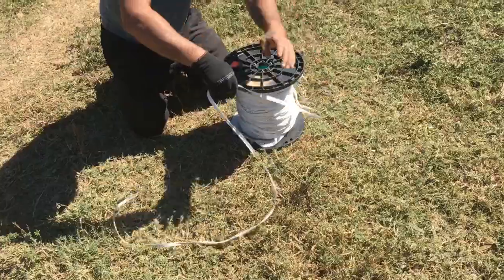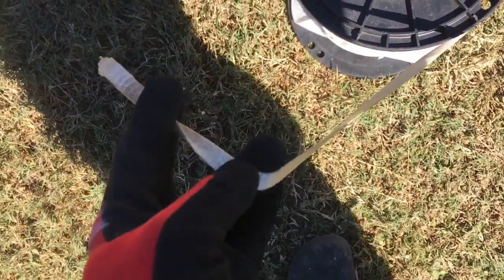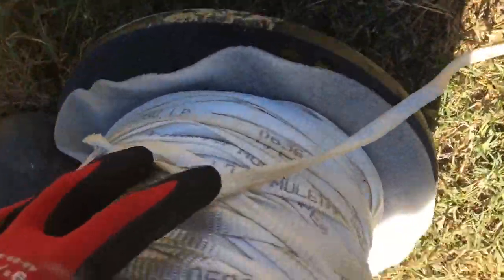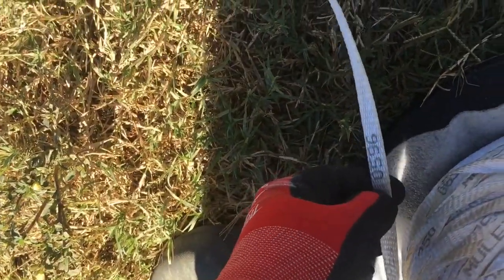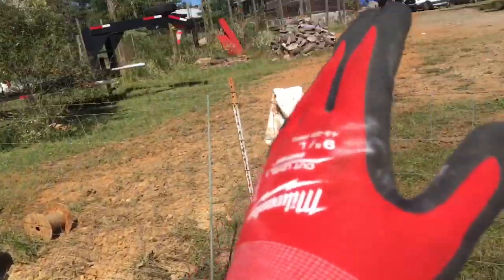Antonio, this is called mule tape — can I see it? This is the cord they're using to pull. This is for pulling electrical. You can also call it pull cord, but it actually says 'mule tape' right on it, and it tells you the break strength. It also has foot markings on it. Usually we'll bury a conduit all the way through, then use a lightweight string and suck it through with a vacuum, then tie this mule tape onto it and pull the mule tape through.